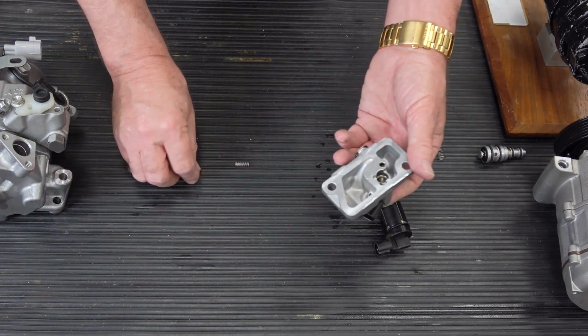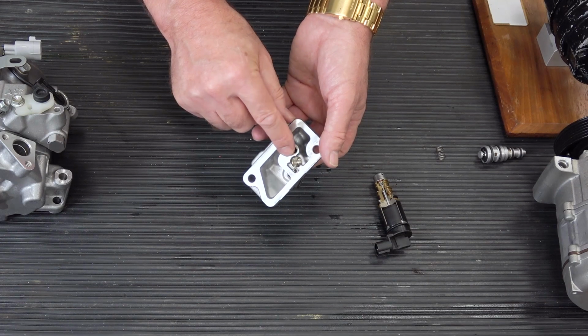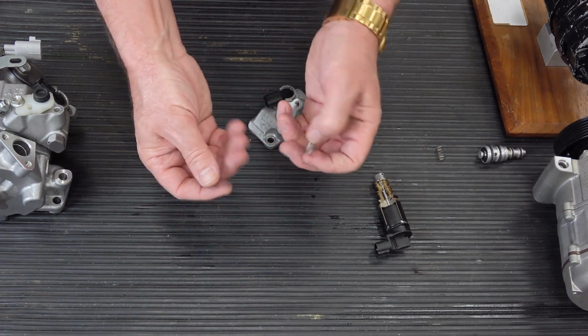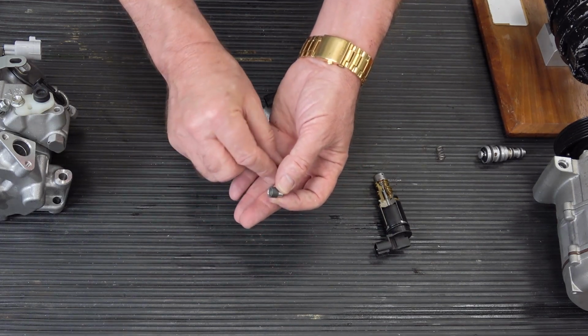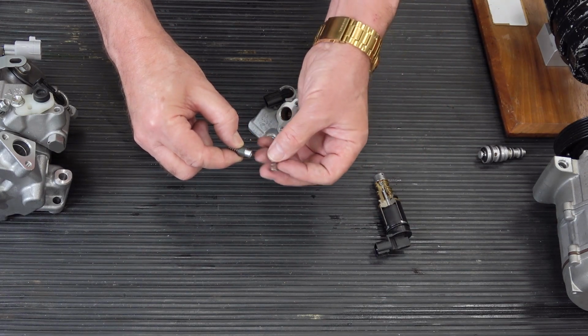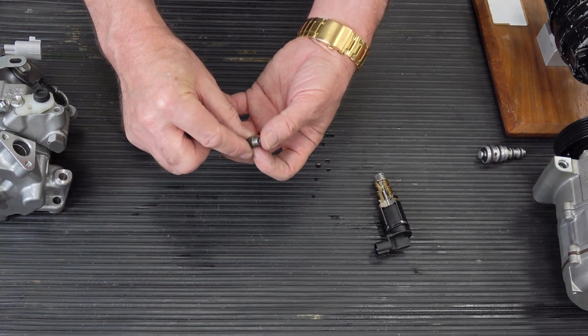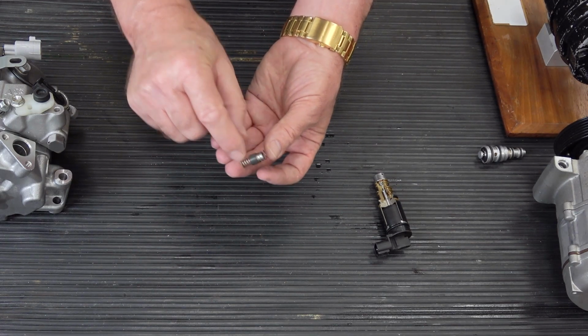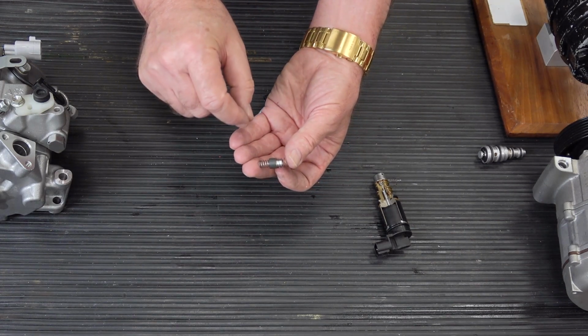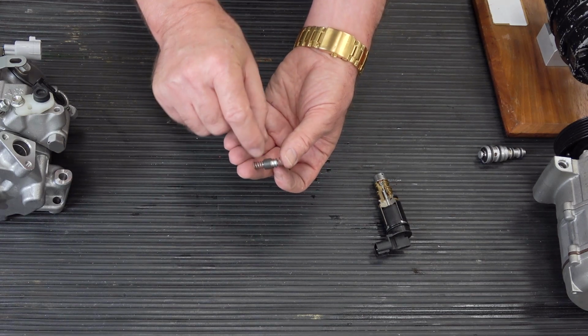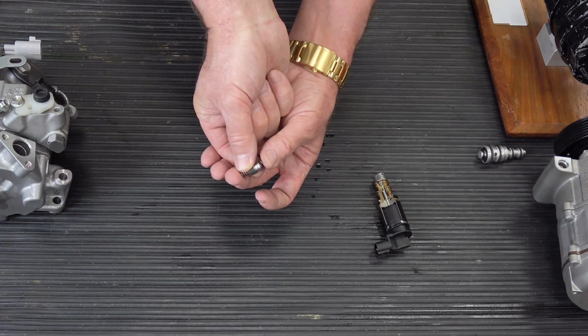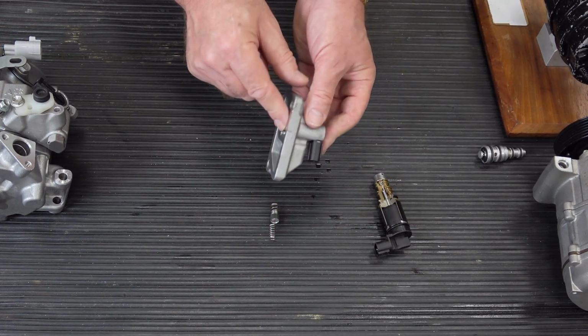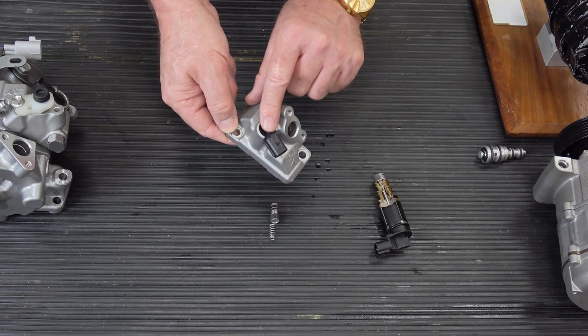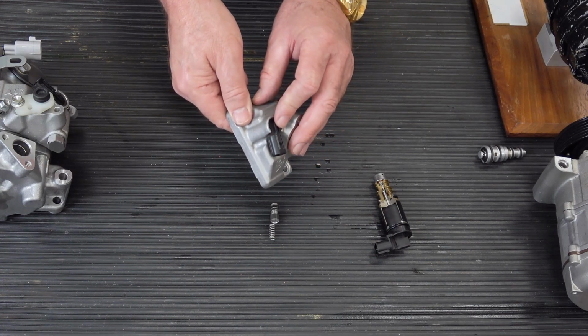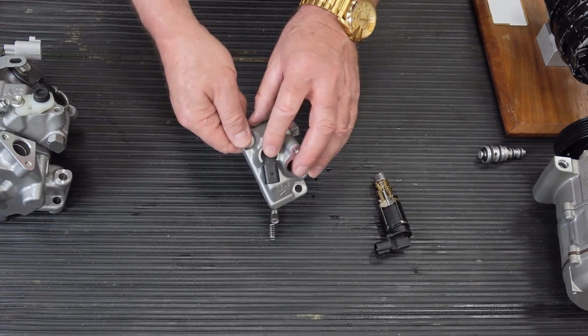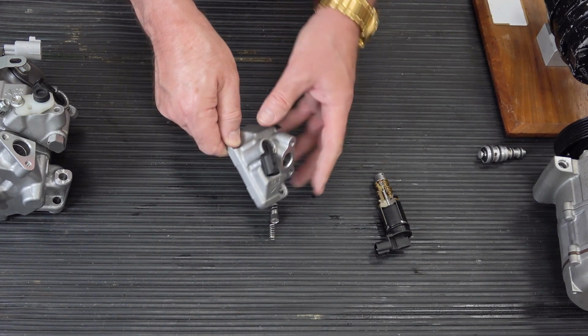What makes this sensor work is that underneath it, inside the discharge manifold, there is a little magnet, like you can see here, and that magnet is balanced between two springs. There's a little shunt passage in here. When the refrigerant starts to flow, the little passage acts as a restriction and deflects the magnet to the left or to the right. This is a Hall effect sensor. As the little magnet moves, it generates a voltage signal, just like a TPS, proportional to the volume of refrigerant flowing through the compressor.